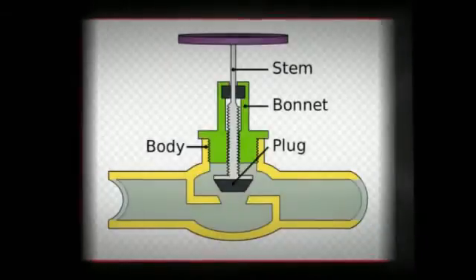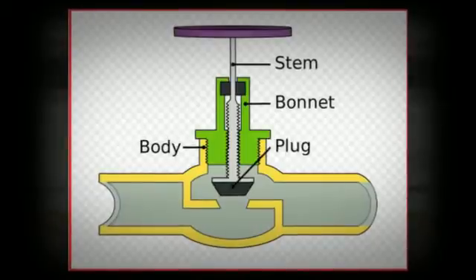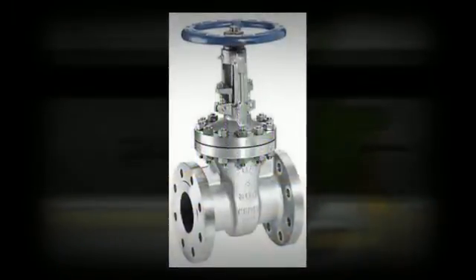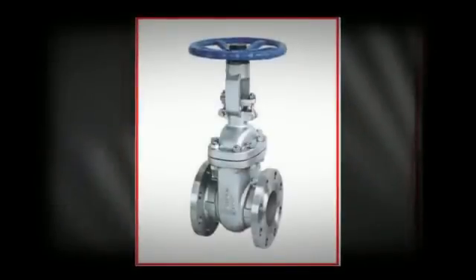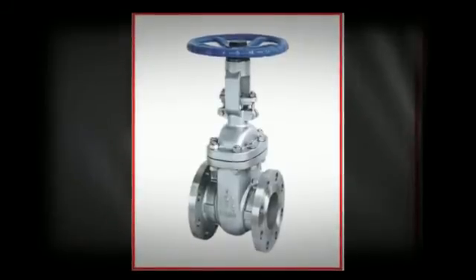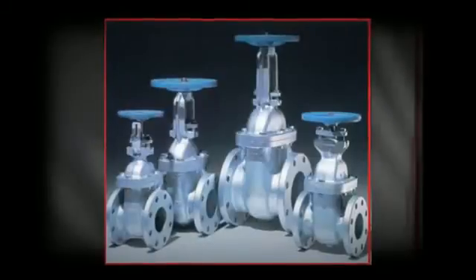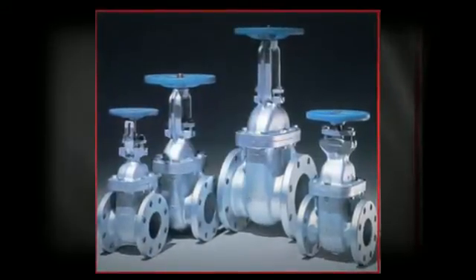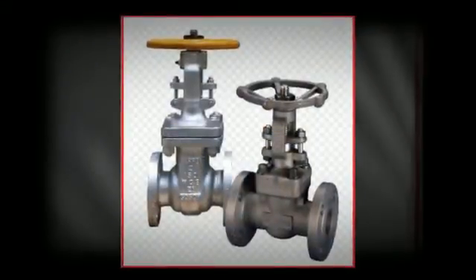Another type of bonnet construction in the gate valve is the pressure seal bonnet. This construction is adopted for valves for high-pressure service, typically in excess of 2,250 pounds per square inch. The unique feature of the pressure seal bonnet is that the body-bonnet joint seal improves as the internal pressure in the valve increases, compared to other constructions where an increase in internal pressure tends to create leaks in the body-bonnet joint.